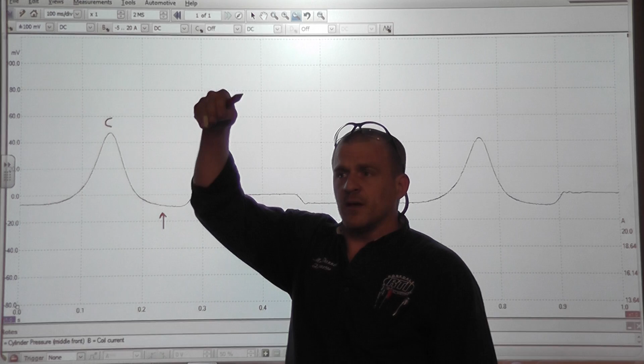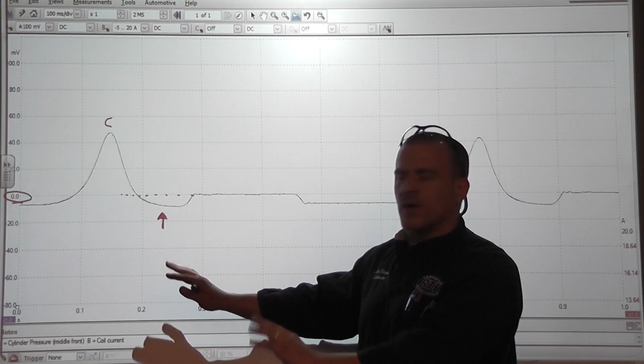This first dip is actually the piston dropping in the cylinder, with the valves closed. The reason we're going into negative pressure - this is your zero line, zero psi right here - is because the valves are closed. They call it an expansion pocket; there's some theory in why it pulls low into a vacuum, but I don't want to focus on that right now. Picture the valves closed and the piston pulling down, creating a vacuum in the cylinder. Again, there's no combustion taking place.